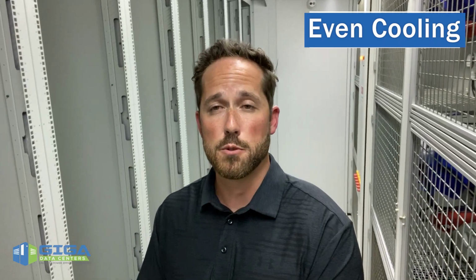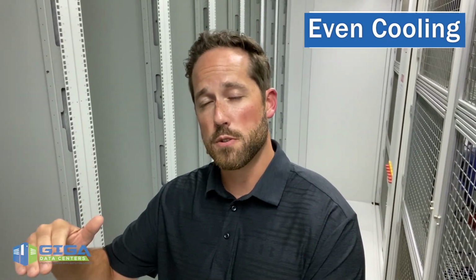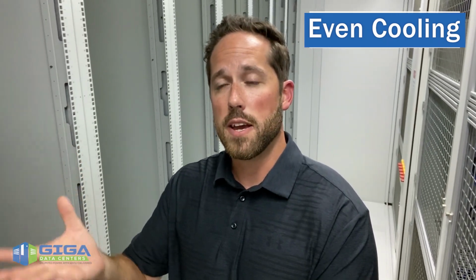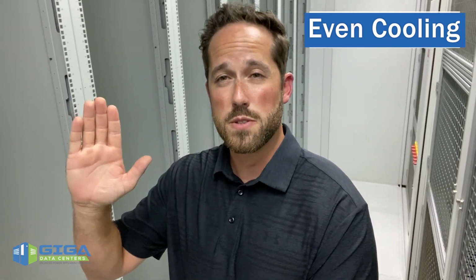Literally floor to ceiling, 4 rows of 3 fans. What this is doing is providing even cooling across the front of any of the equipment living in these IT racks. Again, big differentiator in our facility against a traditional raised floor facility. If we just think about basic science, cold air wants to drop. So if we have a raised floor facility where that particular provider is pumping cold air up through the floor, you may encounter scenarios where, through having to force that air vertical, it may miss some of the equipment lower in the rack. The middle of the rack may get the most of it, and the top of the rack might get whatever's left or isn't sucked in by the equipment in the middle of the rack.